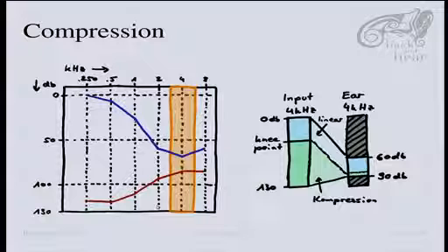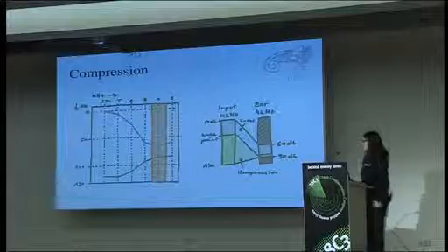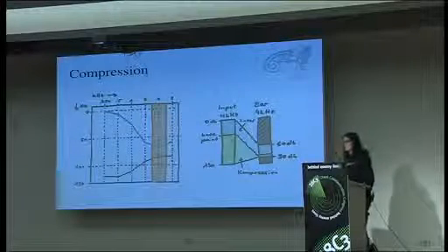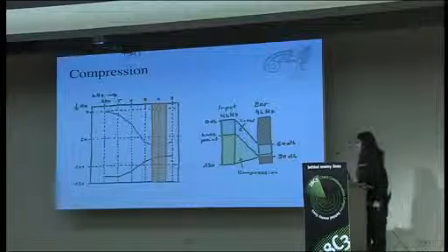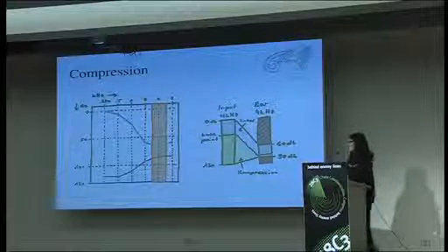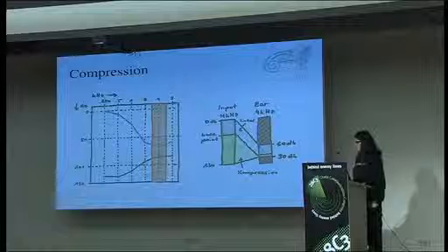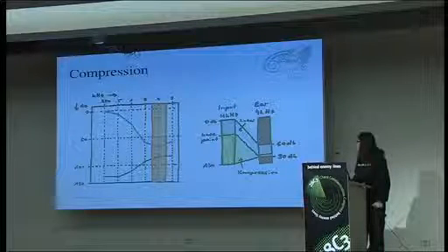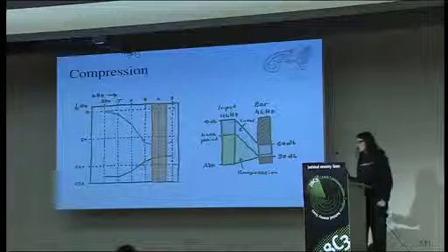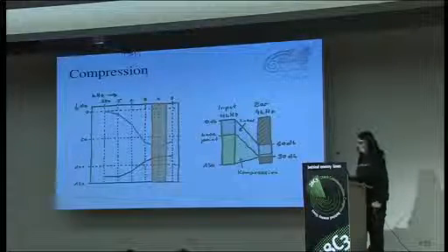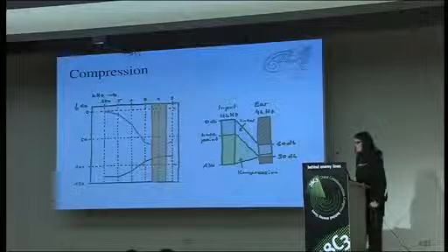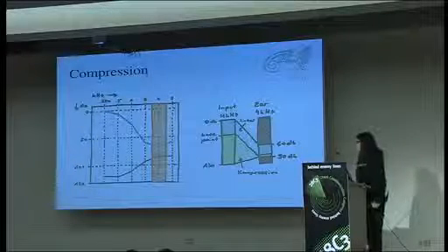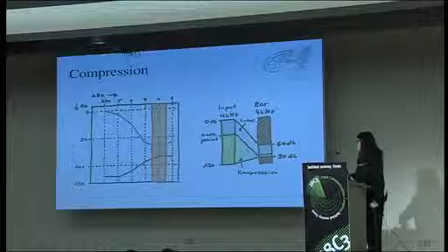This has a problem: if you compress, the volume gets increased and decreased all the time, and this can actually make it harder to understand speech because the hearing aid is adjusting all the time. And so to avoid that, they don't compress every time. The first area here is linearly amplified, and only after a certain level they start compressing, and this is called the knee point. So they usually try to avoid compressing the speech signal and only compress something above that.